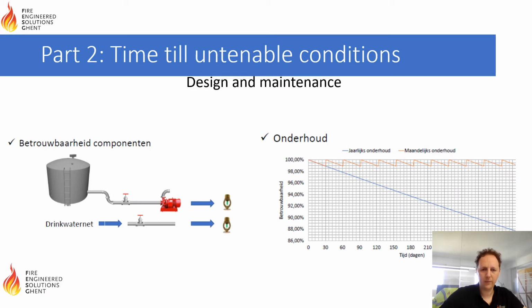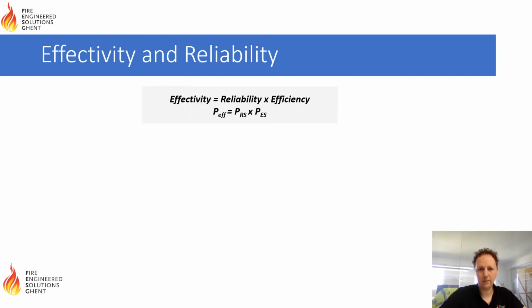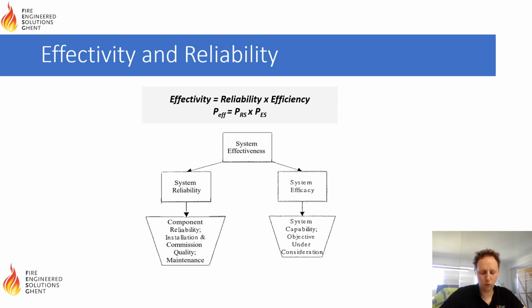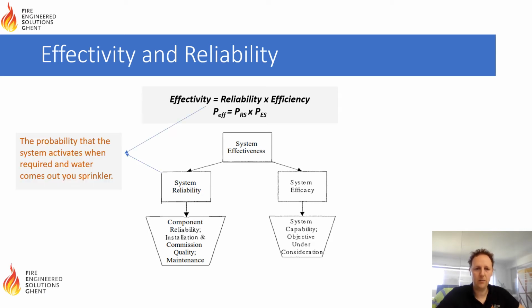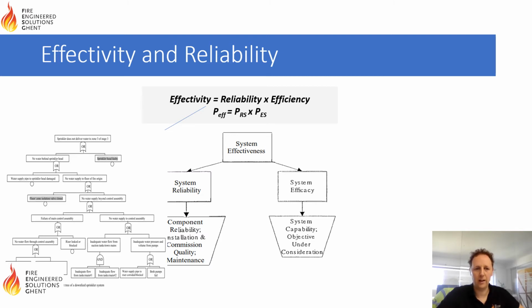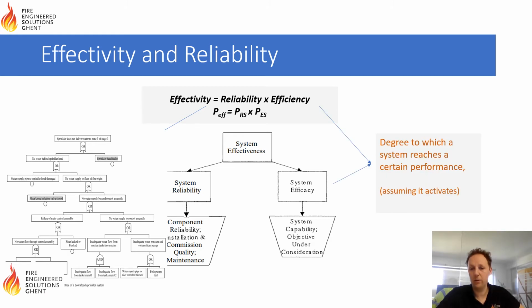Now, what's really important is the reliability of the components. Whenever you can connect your sprinkler to the water main, the reliability becomes higher because there's less components that could fail or valves to be in closed position. We're going to get back to this in a couple of slides, but there's two crucial factors that you should think about when talking about effectivity of a system. One is the reliability, so the probability that the system activates when required, and for instance that water comes out of your sprinkler. For that you can have these fault tree analysis. Second one is the efficiency. The efficiency is the degree to which a system reaches a certain performance, assuming it activates.